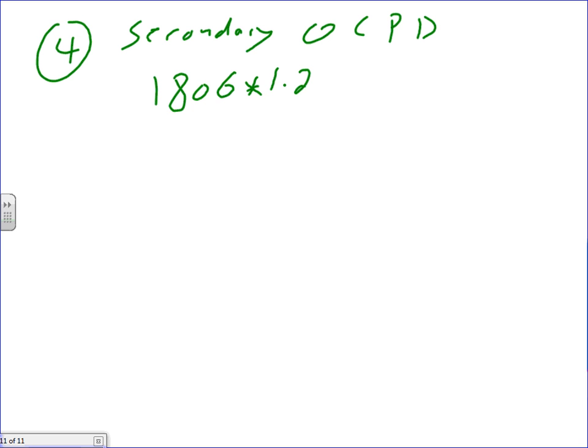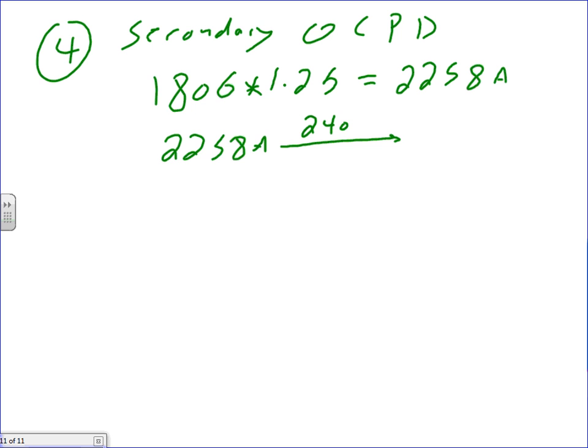Number 4 is system bonding. No, we're going to do the grounding electrode conductor. Secondary overcurrent protection device. Okay, for the secondary overcurrent protection device, guys, we use the same thing, 1806 times 1.25. You end up with the same number, 2258 amps. You're going to take your 2258 amps and land this one on 240.6, and that will get you a 2500 amp device.